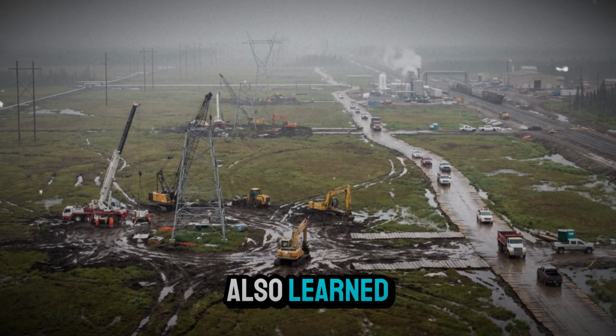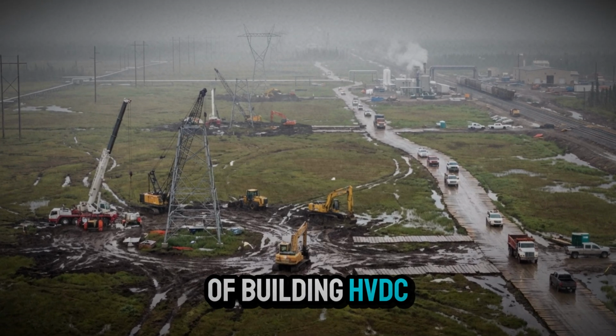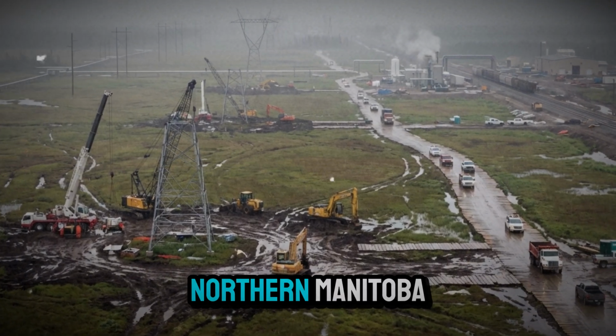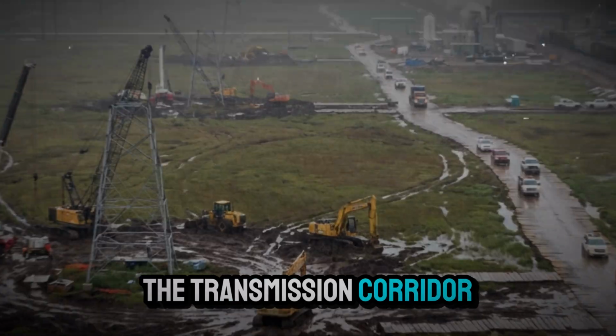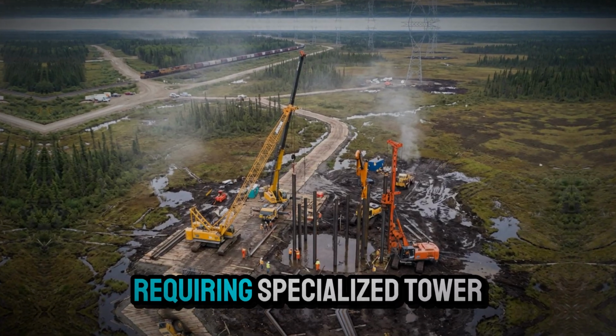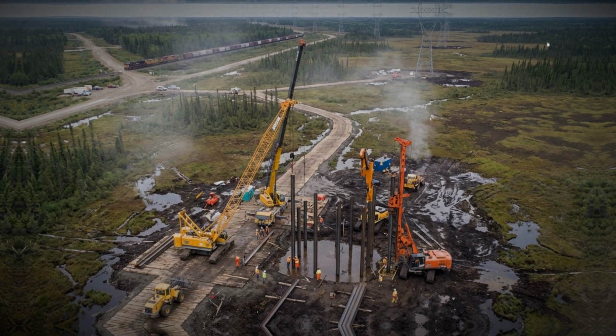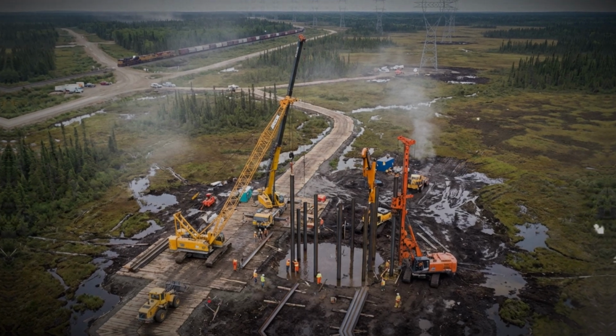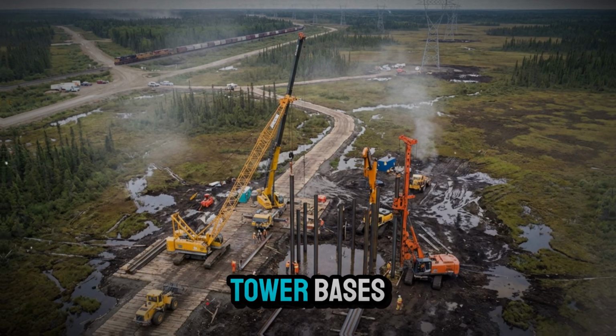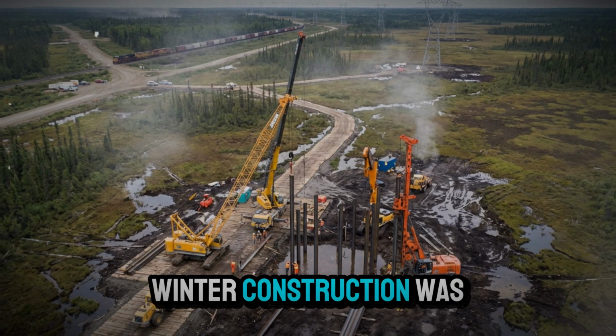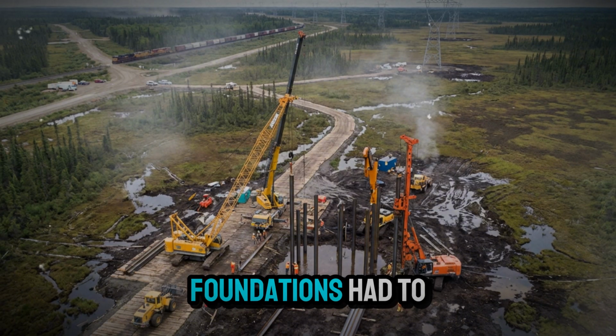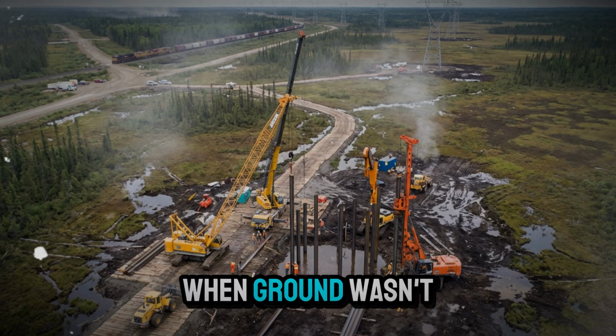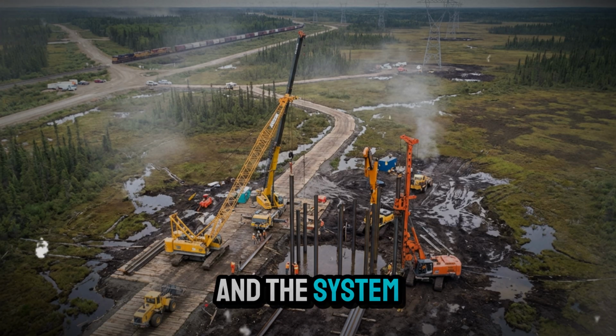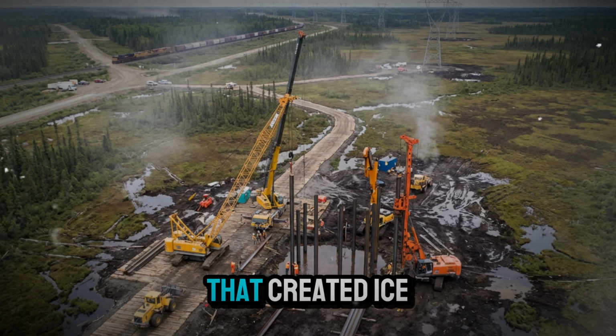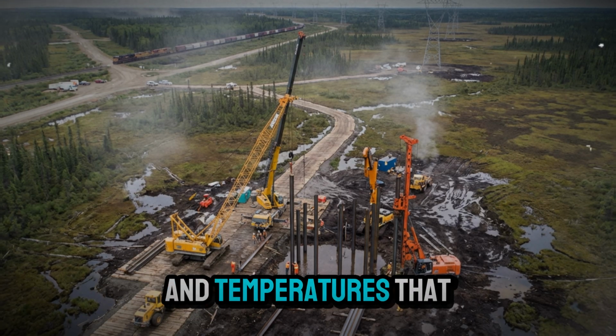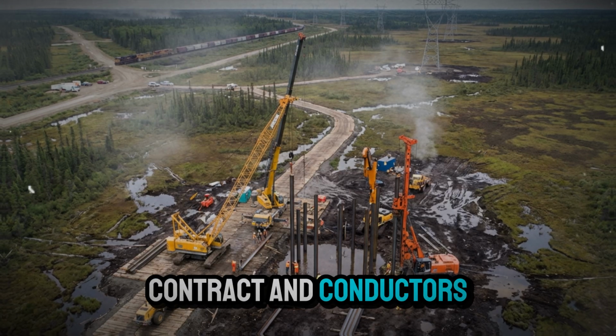Dr. Peterson also learned that nobody had solved the problem of building HVDC infrastructure across terrain like northern Manitoba. The transmission corridor would cross 612 rivers and streams, requiring specialized tower foundations. The route traversed muskeg, waterlogged peat that couldn't support conventional tower bases. Winter construction was impossible. Foundations had to be set during the brief summer months when ground wasn't frozen solid. And the system had to remain operational through winter storms that created ice accumulation on conductors and temperatures that caused metal to contract and conductors to sag.